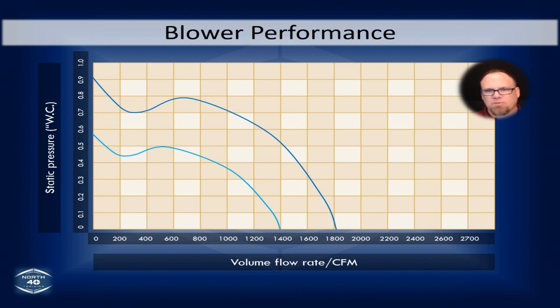Okay, one of the biggest problems that we have: we go out and we put in a brand new furnace, and that brand new furnace is set up to the nines by the efficiency programs that are out there, by the standards that the manufacturers give and the industry gives. So we do everything right. When we leave, the customer goes out and buys a $30 really restrictive filter, puts it in place of the one that we have, which is probably going to be either a 4-inch filter or a fiberglass type filter. And they totally change all the dynamics because they've really restricted that airflow now.